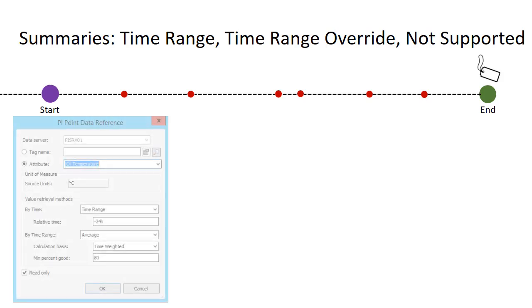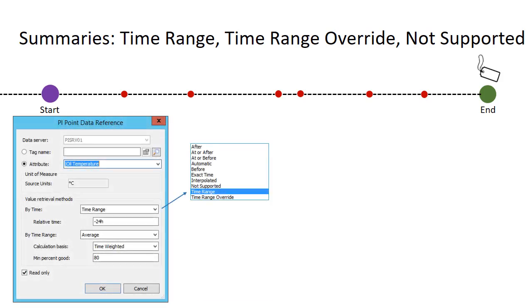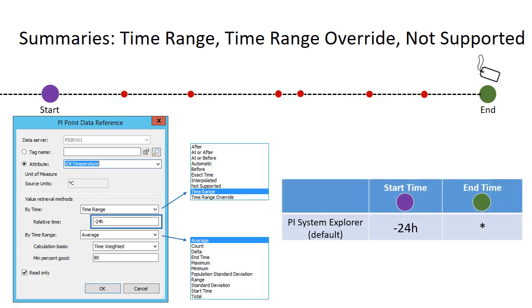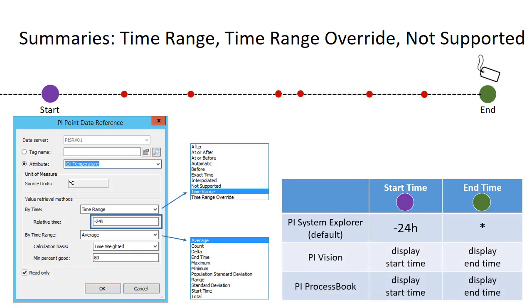Let's start with time range and request a time weighted average. One additional important piece of information is relative time — here we've chosen a relative time of 24 hours. Since PSE by default has an end time context of star but no start time context, the time range used when calculating the average will assume to go back 24 hours into the past from the end time context of star passed by PSE. However, some clients like PI Vision and PI ProcessBook will pass both the start and end time, so the value of 24 hours as the relative time is not actually used by that client.